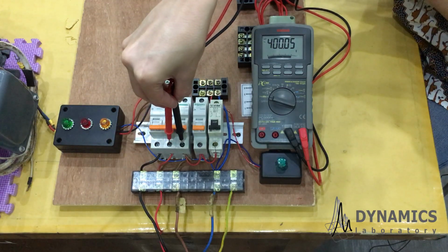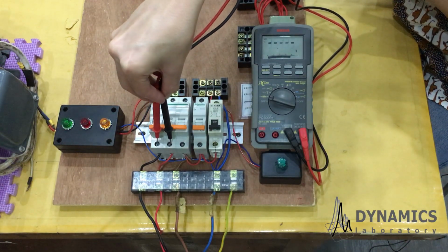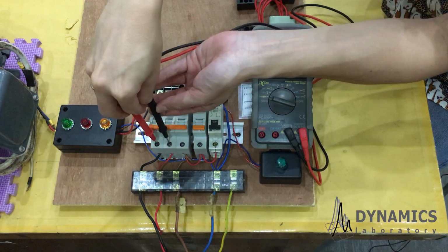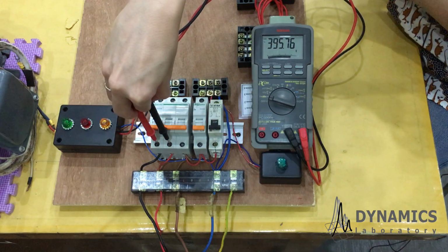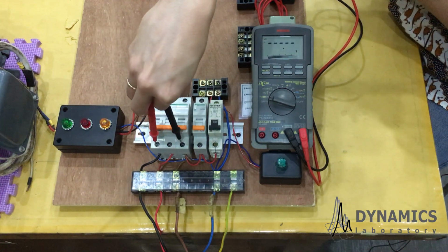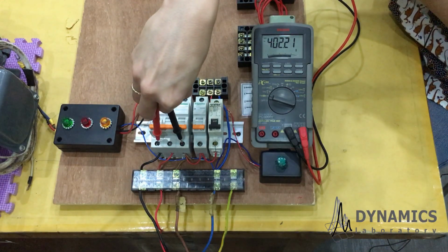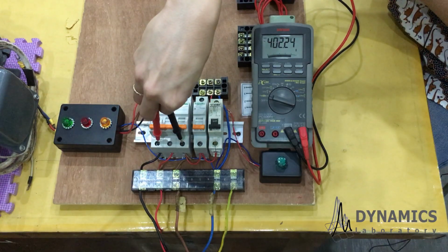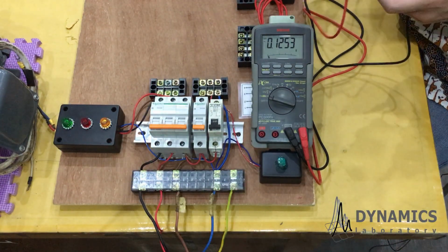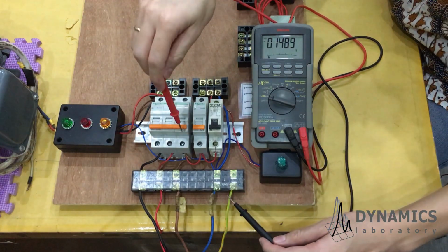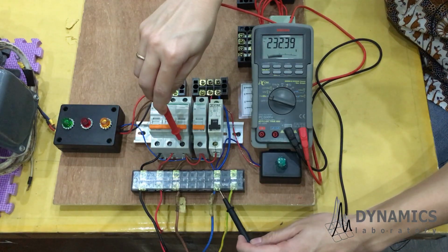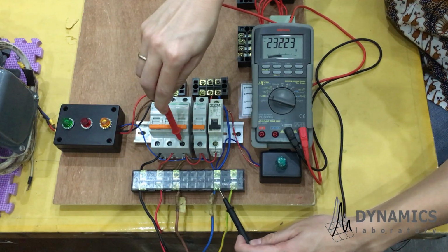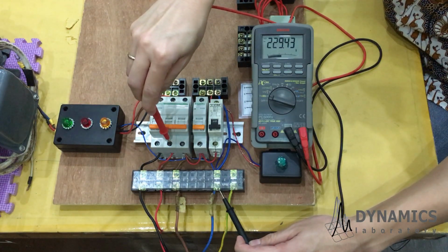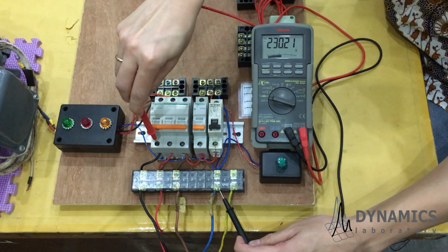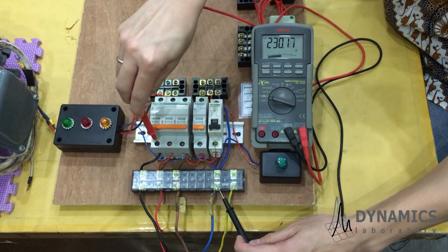R to S, line to line, about 400 volt. And then S to T line, it shows 395. And finally, R to T, 402. And then we also need to measure line to neutral for three-phase grid voltage. R to neutral, 232. And then S to neutral, 229 volt. And then T to neutral, 230 volt.